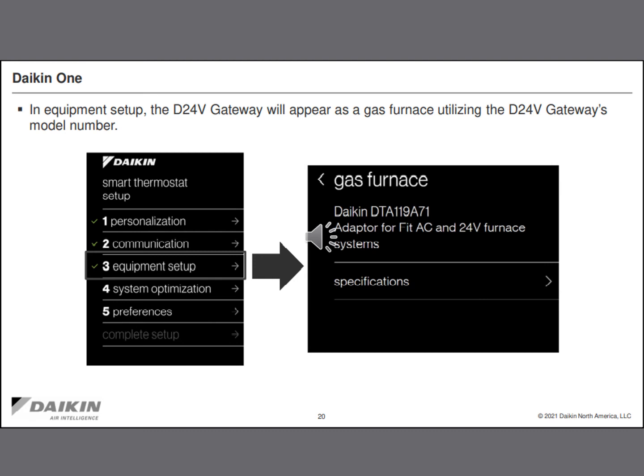Okay, now that we have everything wired up and connected, it's time to commission our equipment here. When you power up the Daikin 1 Plus thermostat and start commissioning it like you normally would a typical FIT system, you'll get to the equipment setup screen. Instead of recognizing a communicating gas furnace, the Daikin 1 thermostat will identify the gateway by the model number, just as an adapter for FIT AC and 24-volt furnace systems. So this takes the place of communicating with that gas furnace, as you see on the screen here.